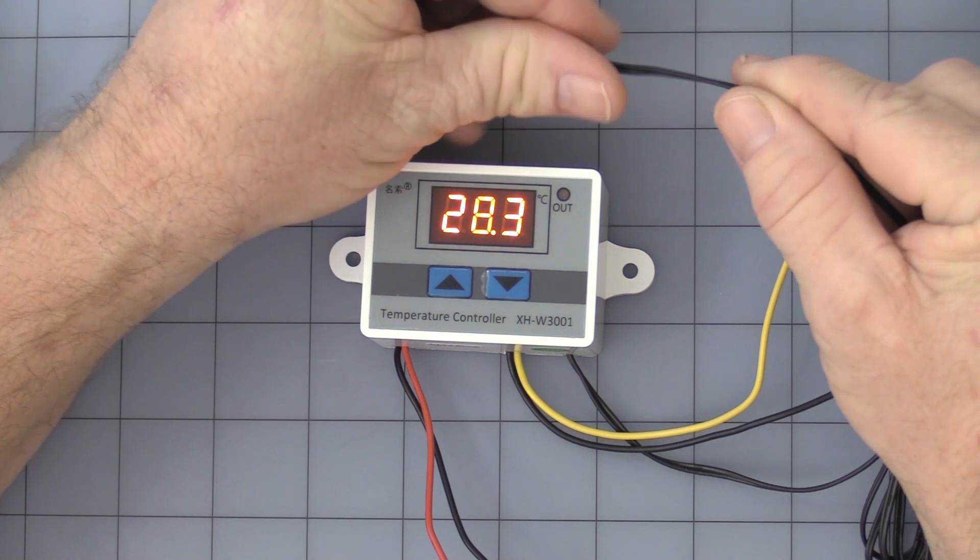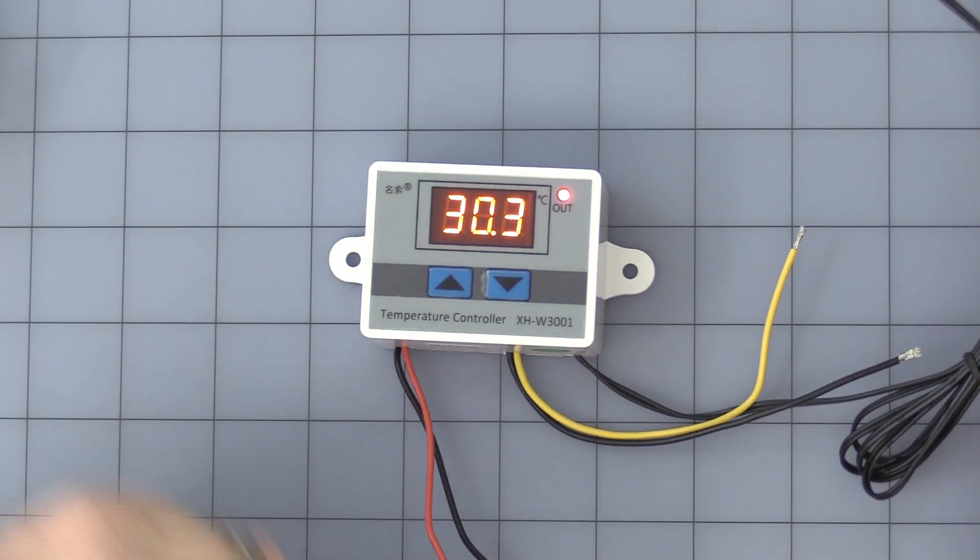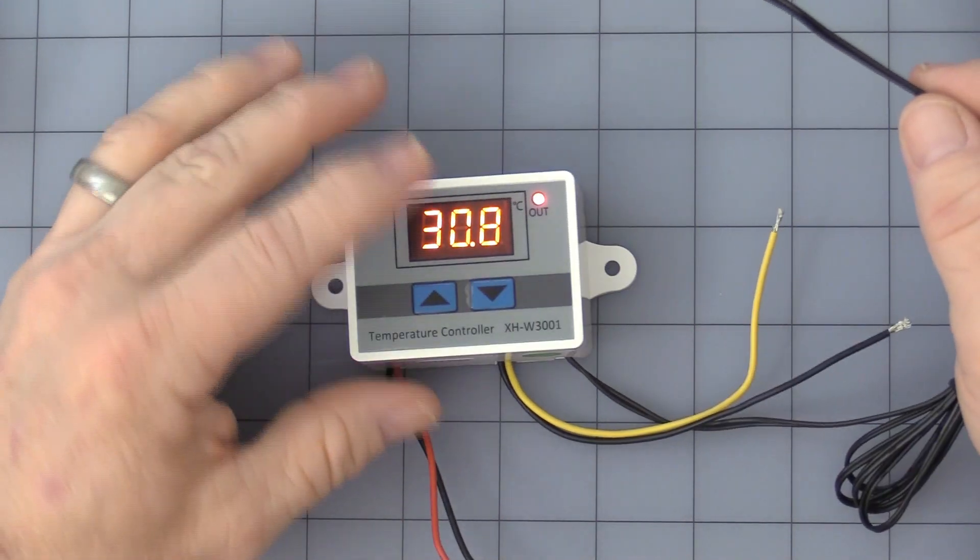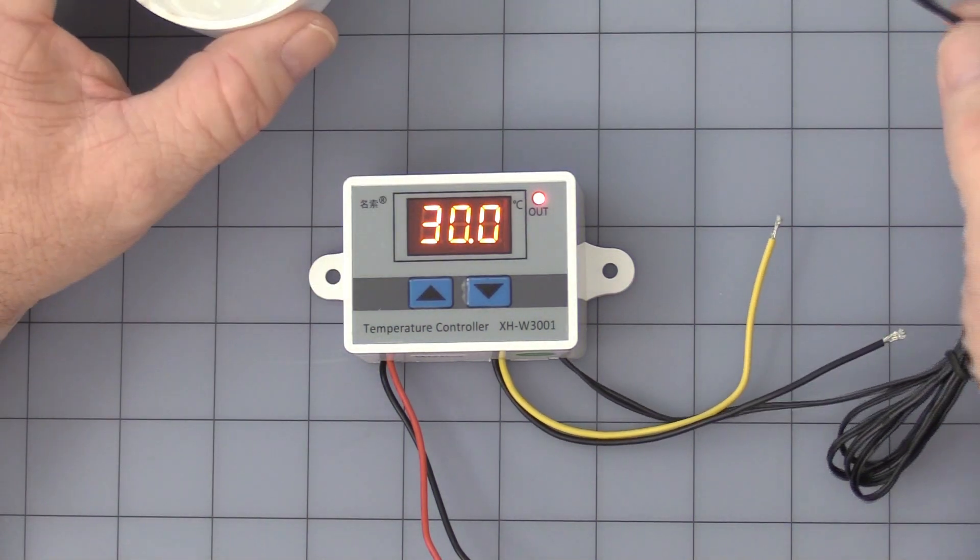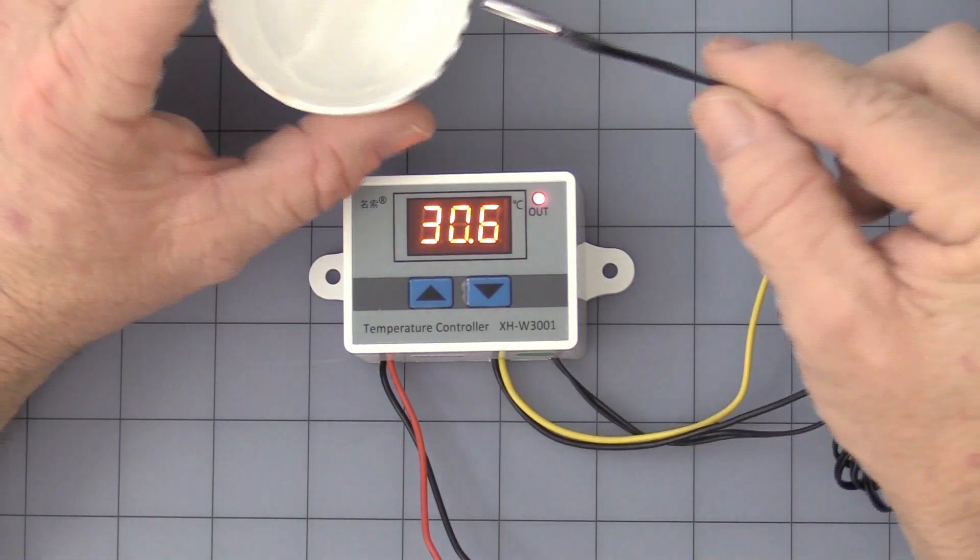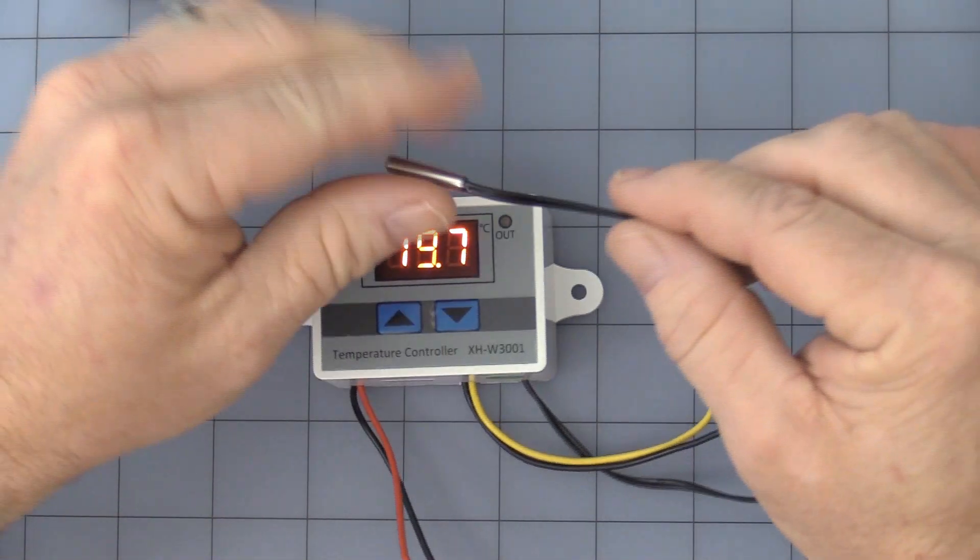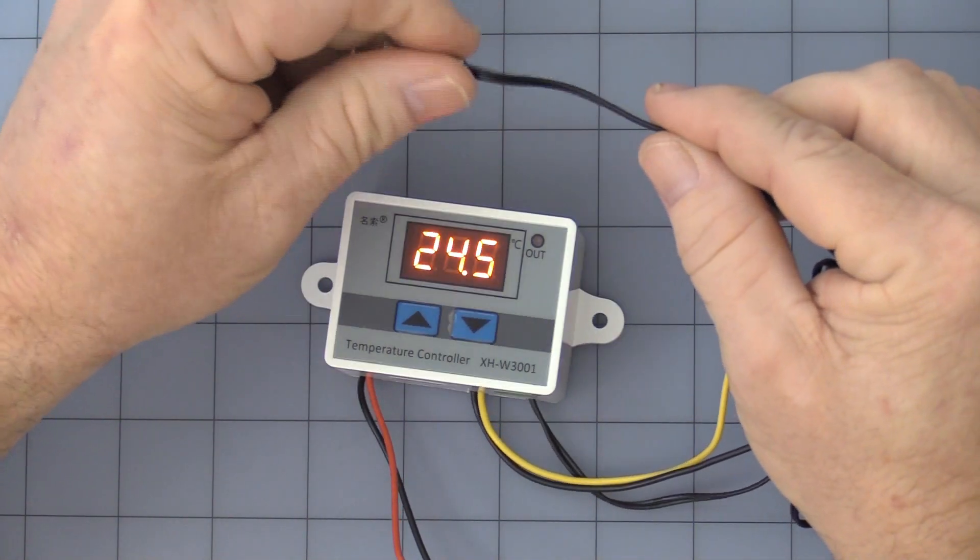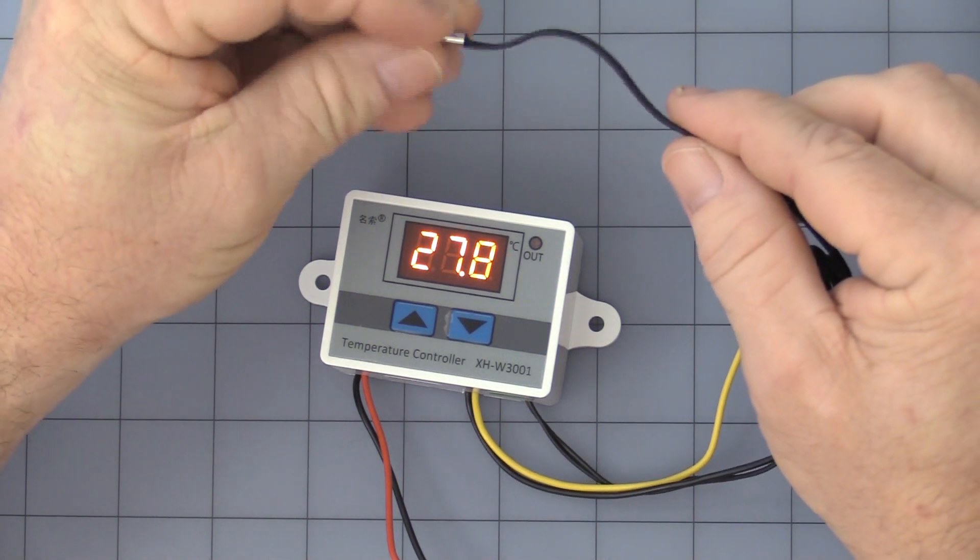Relay turns on and the relay will stay on until we get down to what is it? 24. We'll have that set at 24. Okay. There it turns off. So it's cooled off enough. Once again, once it goes back up to the 30 degree C setting and it turns back on.